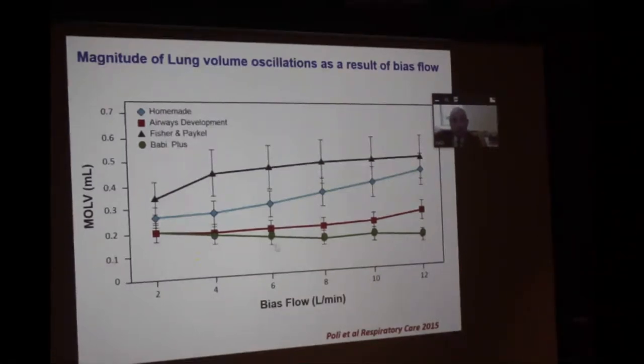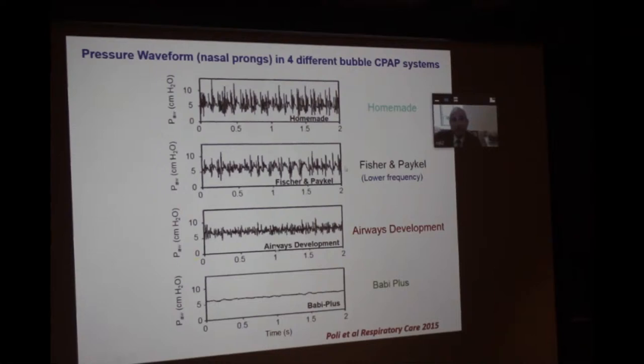One of the reasons is that the Airways Development and Babi Plus systems utilize a diffuser in their bottle, and that diffuser attenuates the oscillations and decreases the interaction between the air and water. So it seems from their data, the Fisher-Paykel and the homemade system perform much better. In addition, if you look at flow rates over 8 liters per minute, the homemade and Fisher-Paykel systems generate second bandwidth frequencies at 54 to 76 hertz and 61 to 71 hertz respectively, which may promote enhanced lung recruitment, especially in an unhealthy lung. The Airways Development and Babi Plus systems don't do that.